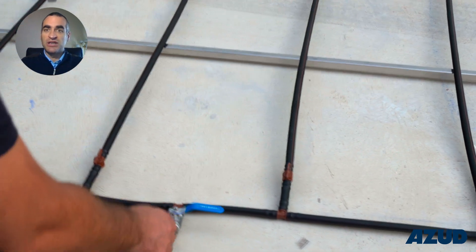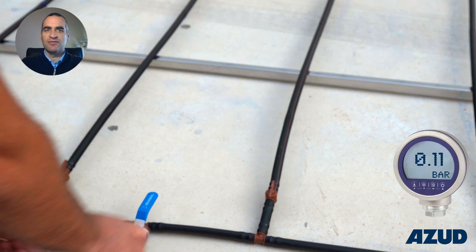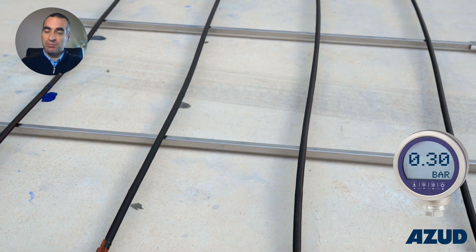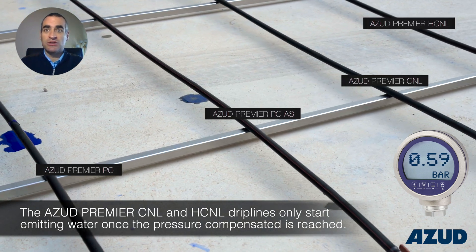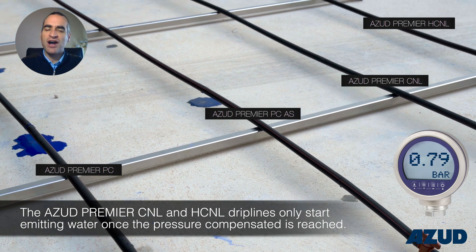The test begins by pressurizing the system and opening the inlet valve. In AZUD PREMIER PC and PC-AS, the water starts to flow almost immediately. In these models, the pressure compensating range starts at 0.5 bar.